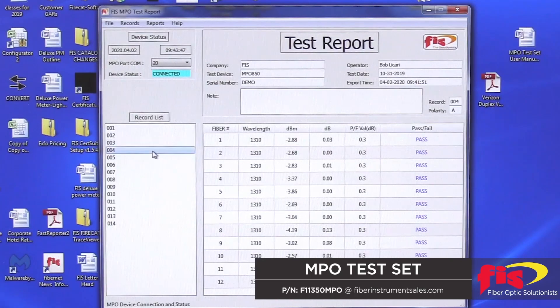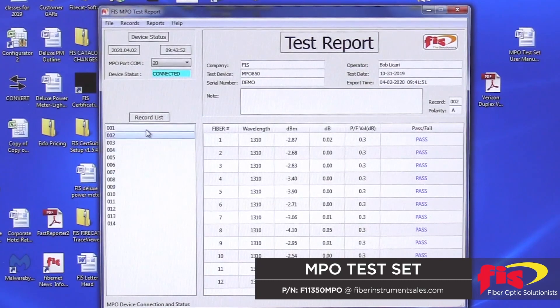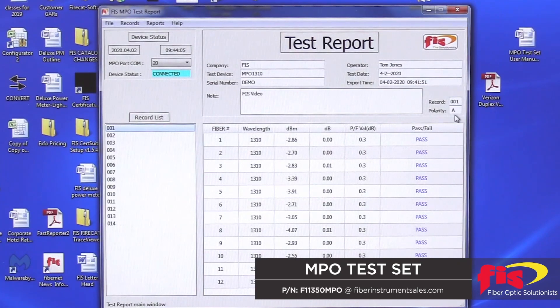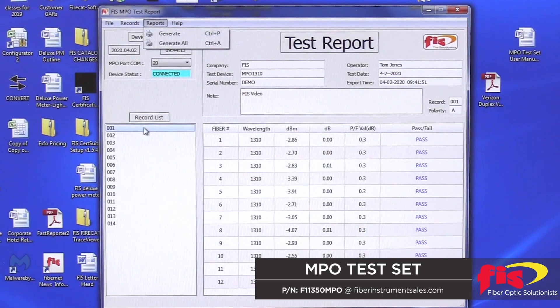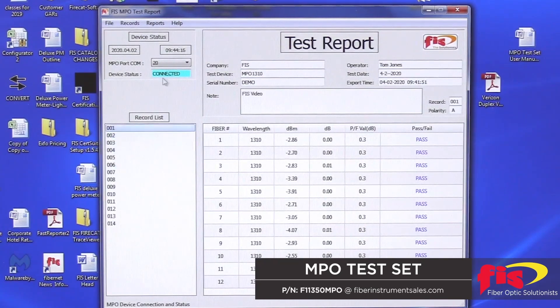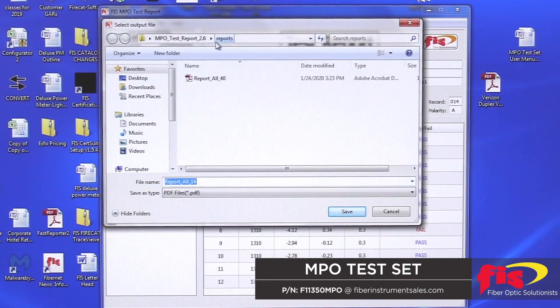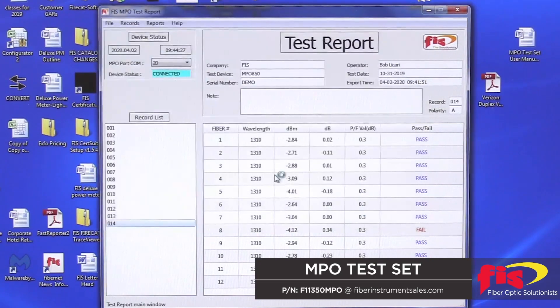You can individually inspect any of the files by clicking on the file number with the mouse. You'll notice that each file has the polarity and wavelength tested, the dBm power output, dB loss value, the pass-fail threshold, and if each fiber passed or failed. At the top, you can fill out the header information as well. When you want to generate the report, go to the top menu and select Reports. You can generate an individual file that's highlighted or generate all currently exported files. Once this selection is made, you have the option to save the report file wherever you like. The report will be saved as a PDF file.